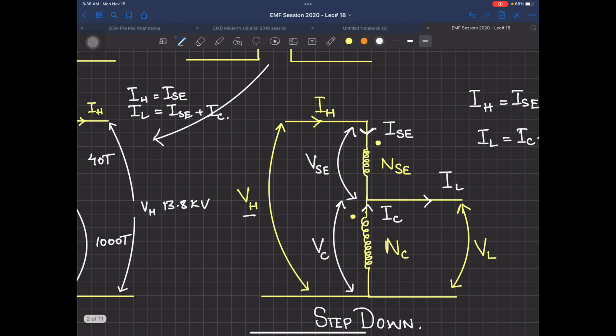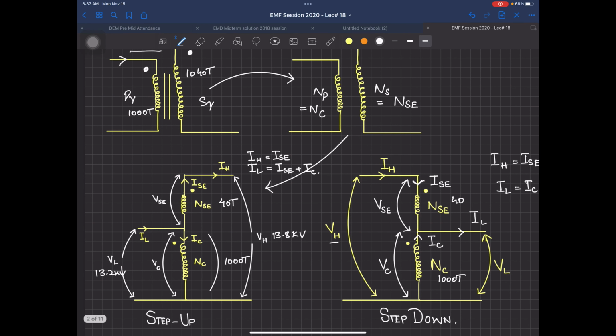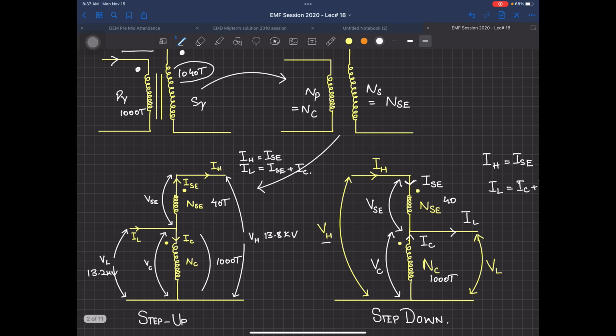Now one thing - if you see step down, it's also working like a voltage divider. For example, if here you have 40 turns and here you have 1000 turns, you apply a voltage here, and across the 1000 turns you take the output voltage. But practically it's still having a transformer core, and that core is actually energized with flux. The only thing you are sacrificing here is isolation, and if isolation is not required, this is the best way of reducing cost, because you don't need an additional 1000 turns on the secondary side.